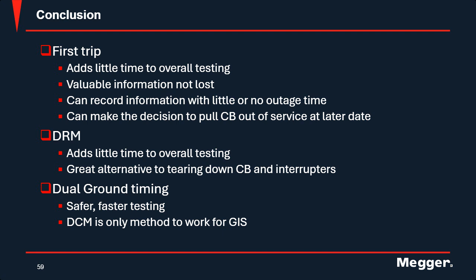And obviously DRM adds a little time as well, but it does give you more information about the interrupter of that circuit breaker, mostly the arcing contact. And then obviously we talked about dual grounding, how it's a safer and faster test. And if you use dynamic contact measurement, it is the only method that works with GIS if you have gas insulated switches.